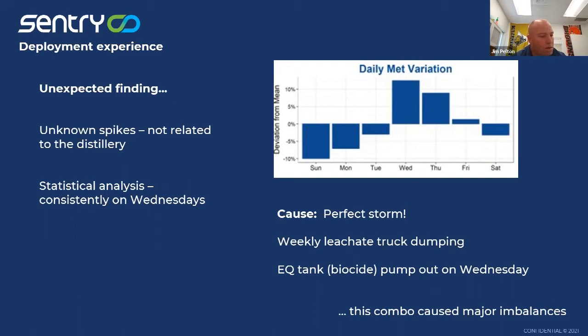And working with Carl, the superintendent over there, he went to his collection guys and asked, what are you doing? What is going on Wednesdays that you guys are sending to my plant? Because it's a CSO facility, they've been very busy over the last 10 years or so building giant EQ basins all over the city. And Wednesdays were the day that they would start pumping down whatever had collected over the last week.